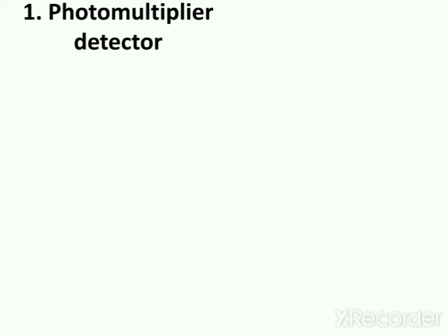Now I am going to discuss the construction and working of the photomultiplier detector. The photomultiplier detector is the most widely used detector in ultraviolet visible spectrophotometer. As the name suggests, it works on the fundamental of multiplication of photoelectrons. The principle employed in this detector is multiplication of photoelectrons by secondary emission of electrons.